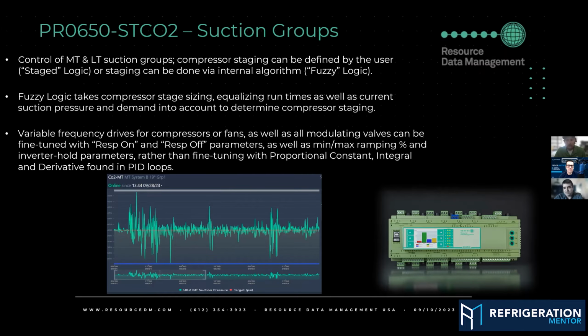So if you have two compressors that are the same size, like maybe 2 and 4 are both 15 horsepower, and 2's been running a lot longer than 4 has, it might say, I'm going to let 2 have a break. We're going to run 4 instead. And then if it needs 2 again, it'll run 2 again.